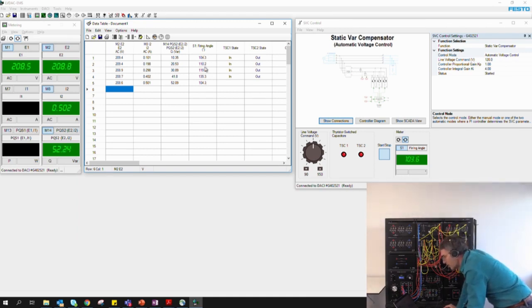As we increase the firing angle, the inductors absorb less and less reactive power. But since we inserted a new bank of capacitors, they need to absorb more to offset some of the reactive power provided by the second bank. That's why the firing angle decreases.